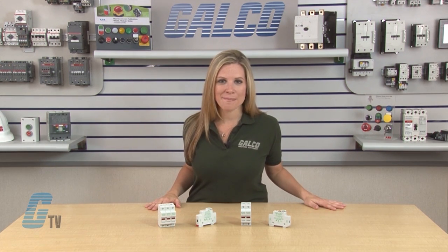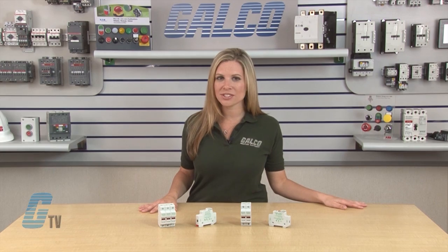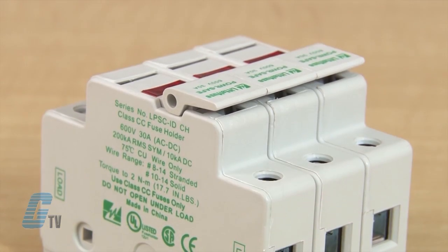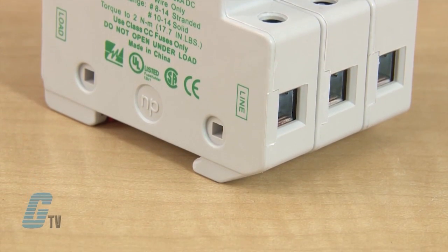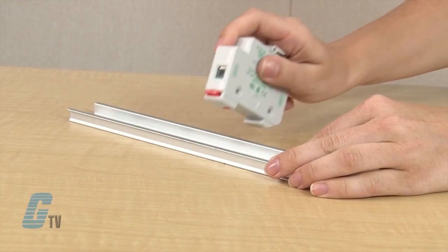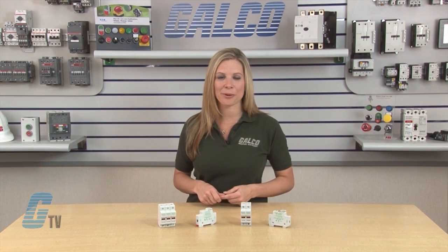Littelfuse Fuse Holders are compact, power safe, dead front holders that provide protection for Class CC and midget style fuses. The housing is made of a thermoplastic material with a ventilated design for cooler operation. They are DIN rail mountable devices and operate at 600 volts AC and DC at 30 amperes.